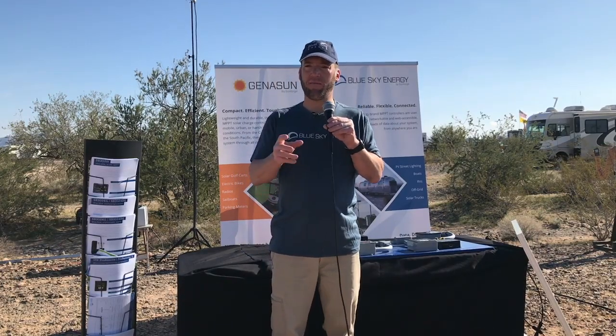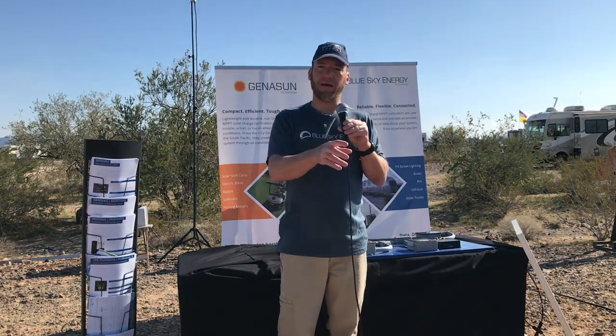It's not that 10 gauge is going to burn up on you, but you're going to lose some efficiency because the voltage at the controller will be less than it could be. So you lose some efficiency to resistance in the wire, but it never becomes a danger.